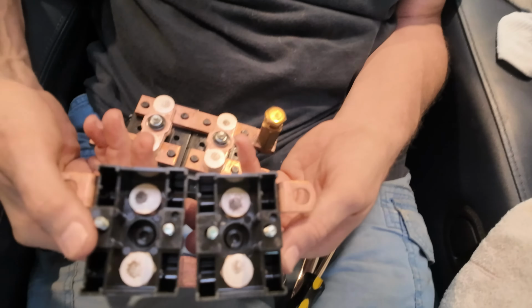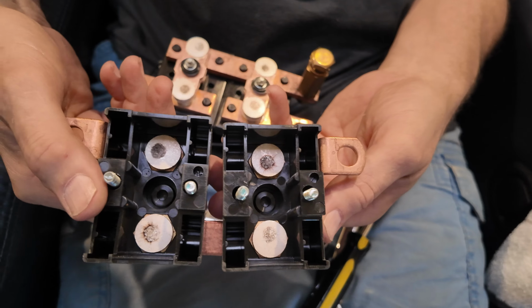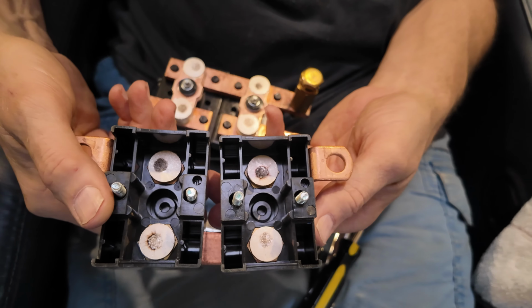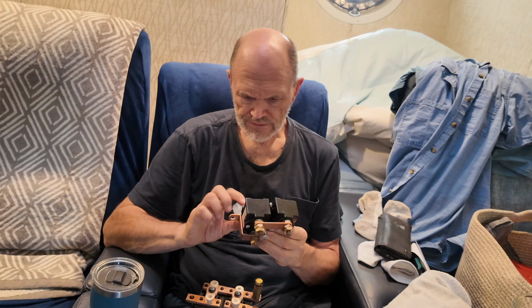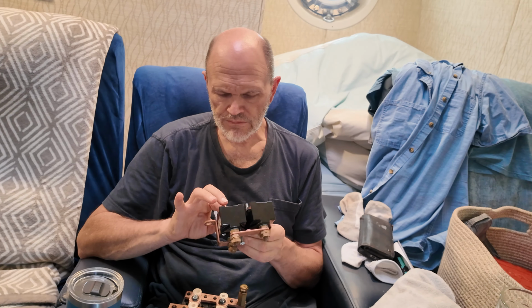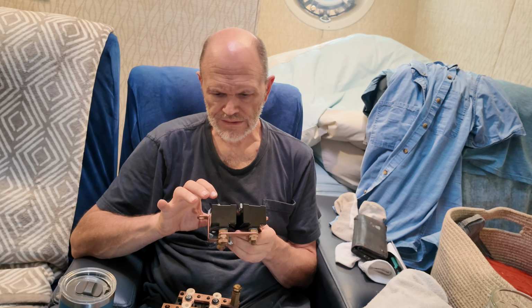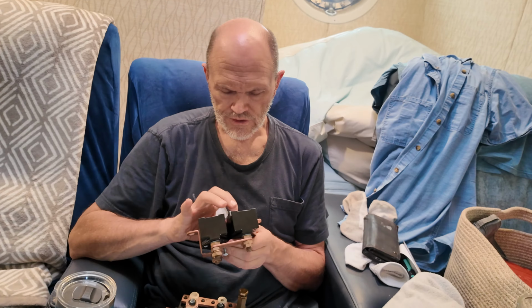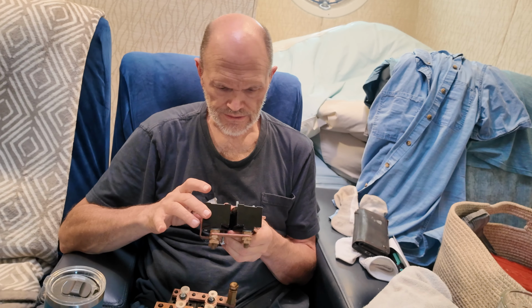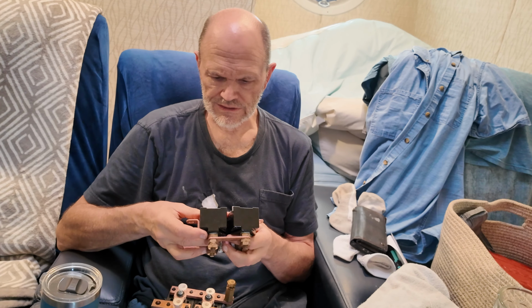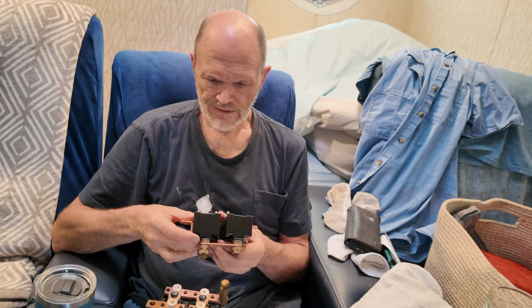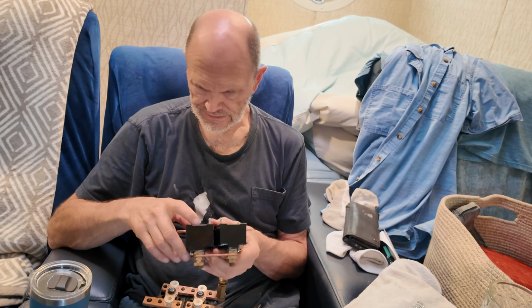Oh yeah, there's quite a bit of arcing inside of there too. You can see the carbonization on those contacts. Clean all that off. What do you clean it with? If it was just the carbon buildup, you could use an eraser, but this has actually pitted it some. So I'm going to have to get a Dremel wheel or something, some little bit of sandpaper that can get up in there and clean this off.